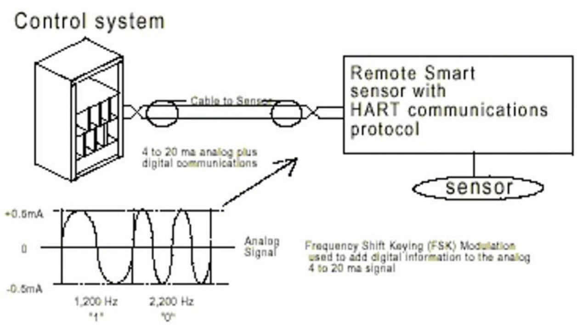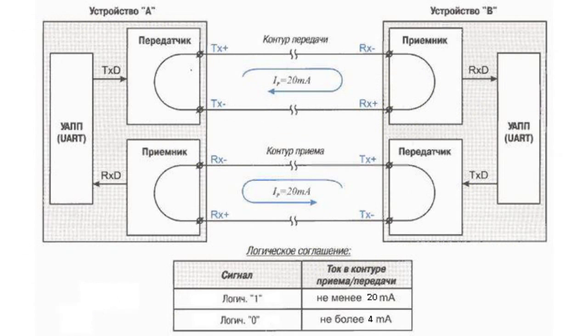The analog current loop transmits analog signals via paired wires as part of laboratory equipment and production control systems. It uses an offset band of 4-20 mA. The lowest signal value corresponds to 4 mA and the highest signal value equals 20 mA.